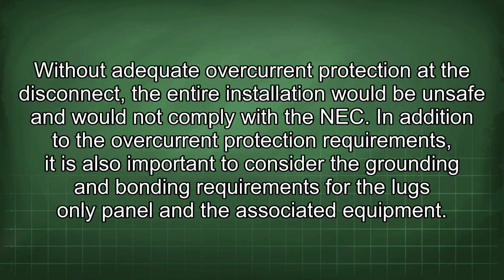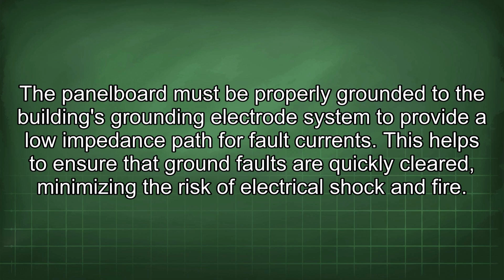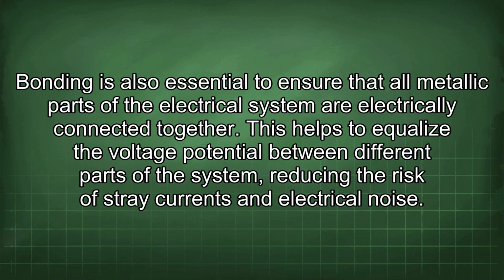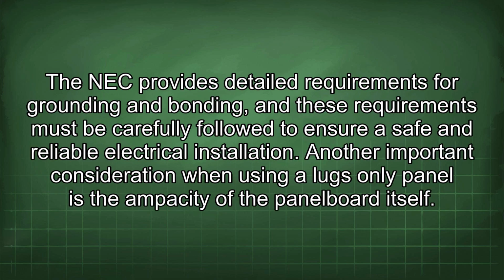In addition to the overcurrent protection requirements, it is also important to consider the grounding and bonding requirements for the lugs-only panel and the associated equipment. The panel board must be properly grounded to the building's grounding electrode system to provide a low impedance path for fault currents. This helps to ensure that ground faults are quickly cleared, minimizing the risk of electrical shock and fire. Bonding is also essential to ensure that all metallic parts of the electrical system are electrically connected together. This helps to equalize the voltage potential between different parts of the system, reducing the risk of stray currents and electrical noise. The NEC provides detailed requirements for grounding and bonding, and these requirements must be carefully followed to ensure a safe and reliable electrical installation.